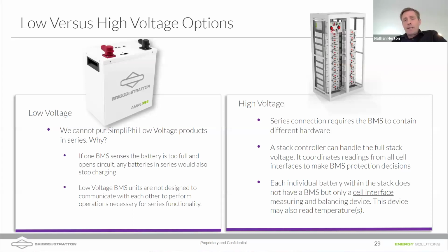A lot of these things are programmed into the BMS. For instance, balancing of battery cells happens on charge cycles when those cells get a little over 54.4 volts, which I believe is the threshold for balancing. So if you have a lithium battery system, you want to occasionally charge it to 100%. You don't want to constantly cycle the battery between 20 and 60% state of charge a thousand times in a row without getting it to a full charge occasionally. That's a function of the BMS.